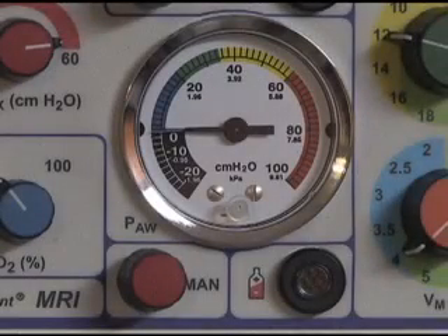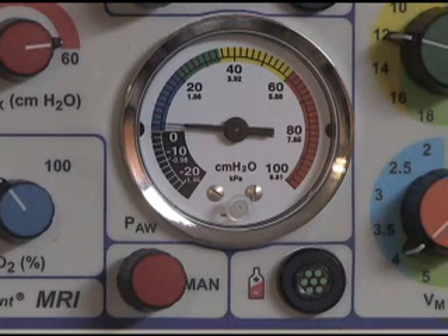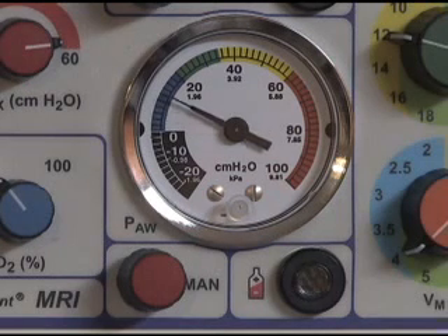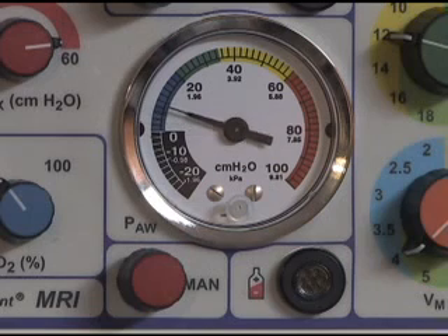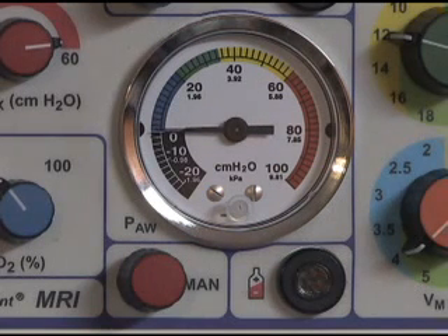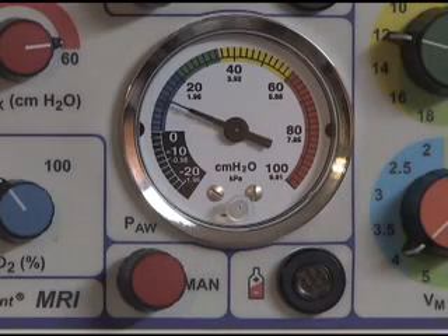When the gas supply is turned on, the green visual gas supply indicator will turn from black to green, and a short audible tone will be heard confirming that the gas is available. When the gas supply drops below the minimum safe operating pressure of 40.6 pounds per square inch, the indicator will flash black and green and a low-pitch audible oscillating alarm will sound. The oscillation frequency decreases as the input pressure reduces to the point where the alarm will emit a continuous tone, indicating that the gas supply is no longer providing sufficient pressure for full ventilator function.